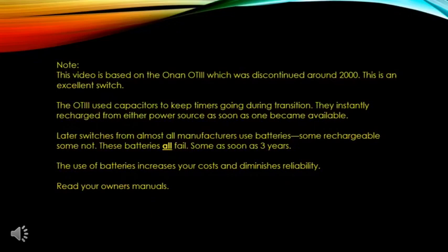This video is based on the Onan OT3 transfer switch, which was discontinued around 2000. It's an excellent switch — the OT3 used capacitors to keep the timers going during transition, instantly recharging from either power source as soon as one became available. Later switches from almost all manufacturers use batteries. Some are rechargeable, some are not. These batteries all fail — some as soon as three years. The use of batteries increases your cost and diminishes reliability. Read your owner's manual and service the batteries regularly.